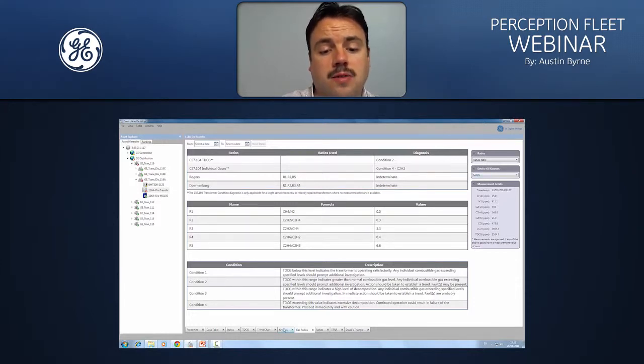And then finally we have our key gas, which again has our statistical matching. You can see we statistically match which of these particular conditions we feel is closest to the gas pattern that's in the multi-gas product. You can see, for example, in here we're saying we're 84% sure that this particular device is experiencing corona partial discharge.